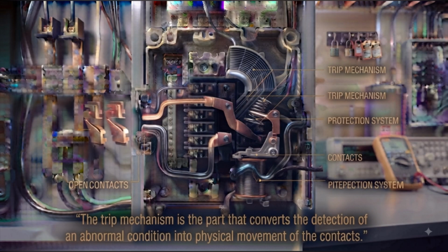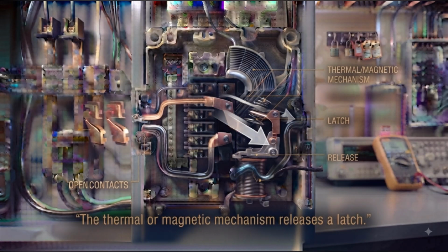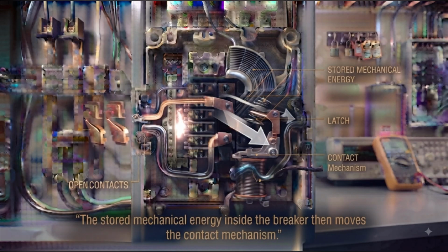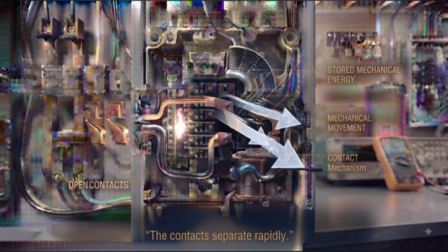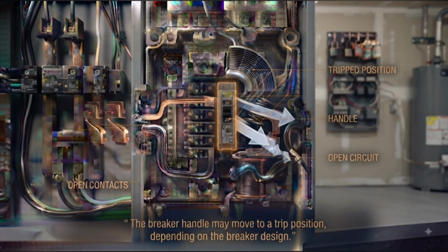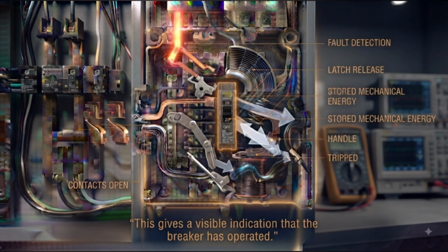The trip mechanism. The trip mechanism is the part that converts the detection of an abnormal condition into physical movement of the contacts. The thermal or magnetic mechanism releases a latch. The stored mechanical energy inside the breaker then moves the contact mechanism. The contacts separate rapidly. The breaker handle may move to a trip position, depending on the breaker design. This gives a visible indication that the breaker has operated.